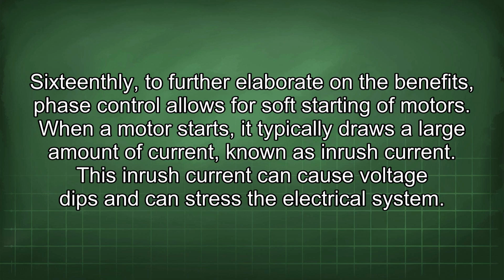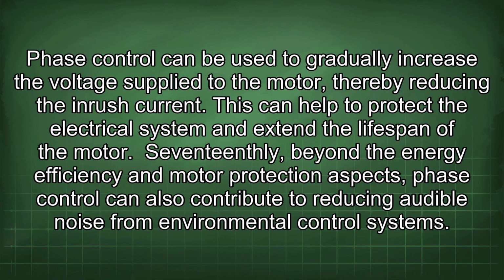16thly, to further elaborate on the benefits, phase control allows for soft starting of motors. When a motor starts, it typically draws a large amount of current, known as inrush current. This inrush current can cause voltage dips and can stress the electrical system. Phase control can be used to gradually increase the voltage supply to the motor, thereby reducing the inrush current. This can help to protect the electrical system and extend the lifespan of the motor.